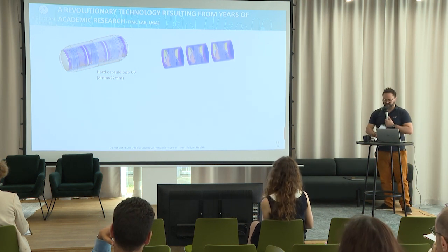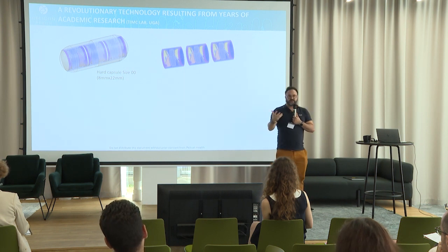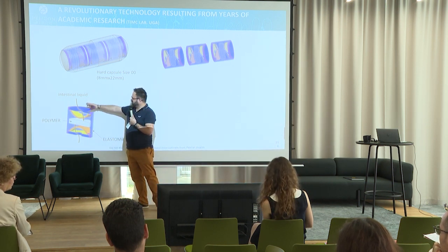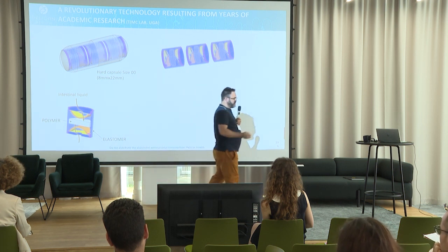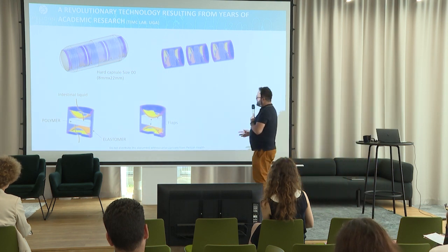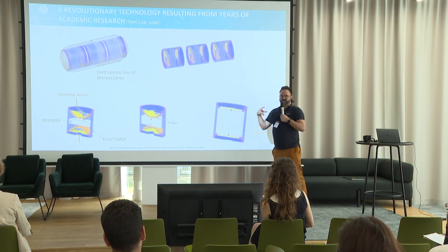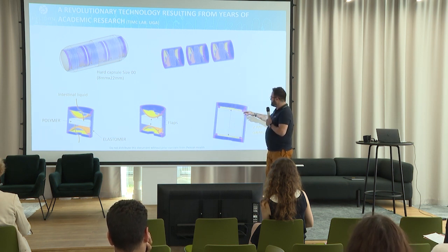Within that, you have the three sampling modules that are made out of silicone. It's colored, so it's easier to retrieve. It's also radio opaque, so it can be found inside the body with a scan and an X-ray. On each side of the module, you have two opening holes, sampling holes, that allow the intestinal liquid to flow in. At the heart of the device, you have that sponge polymer that is super absorbent. Once the liquid touches that sponge, the sponge will slowly expand, slowly swell, and it will start pushing on closing flaps once the sample has been taken fully. The device grows a little bit because it's stretchy, and the closing flaps are completely placed and shut off the device, so nothing goes out, nothing goes in.